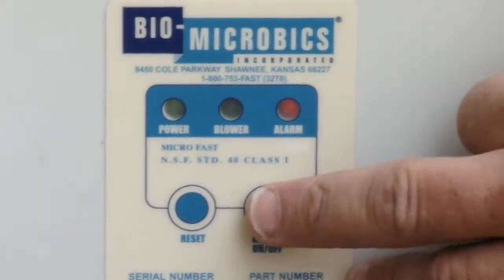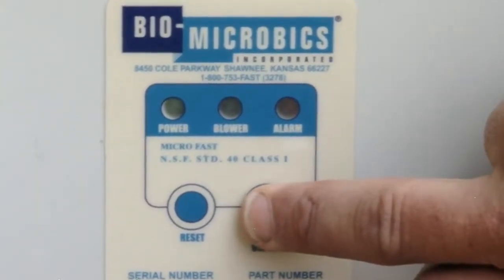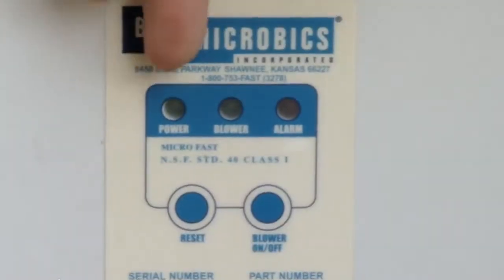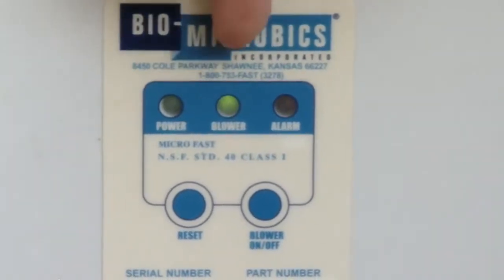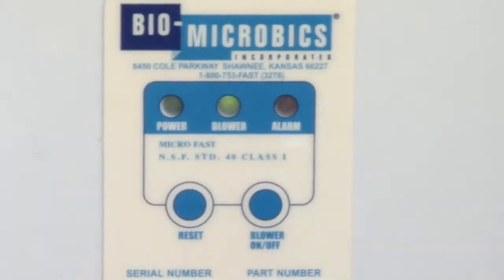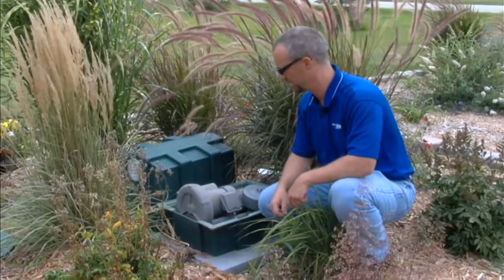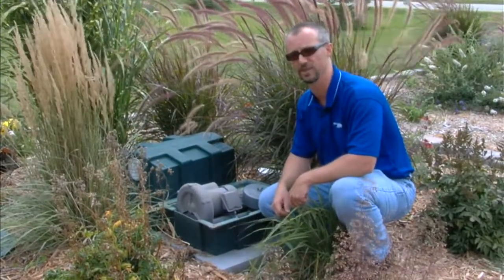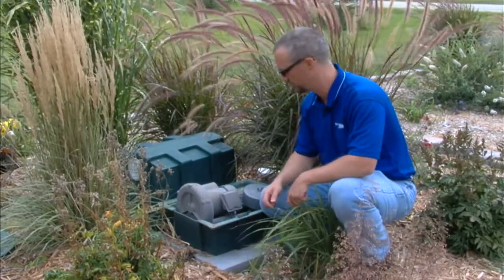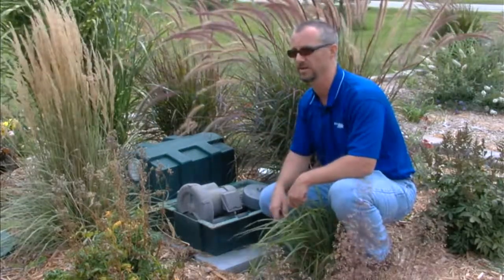Turn the blower back on. Simply hold down the blower button for about 3 seconds. Your power light will start to flash, and then your blower will kick on and your blower light comes on. Okay, now we're going to check the electrical on the blower, check the amp draw on the blower. First thing we need to do in order to do that is shut off the power at the control panel.